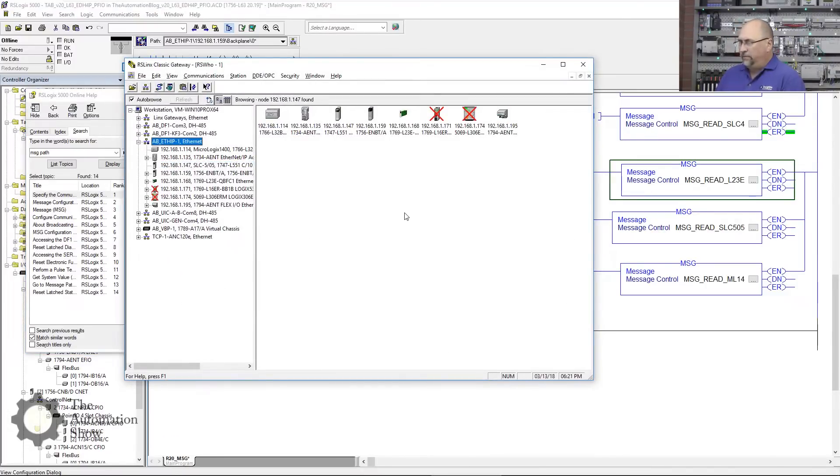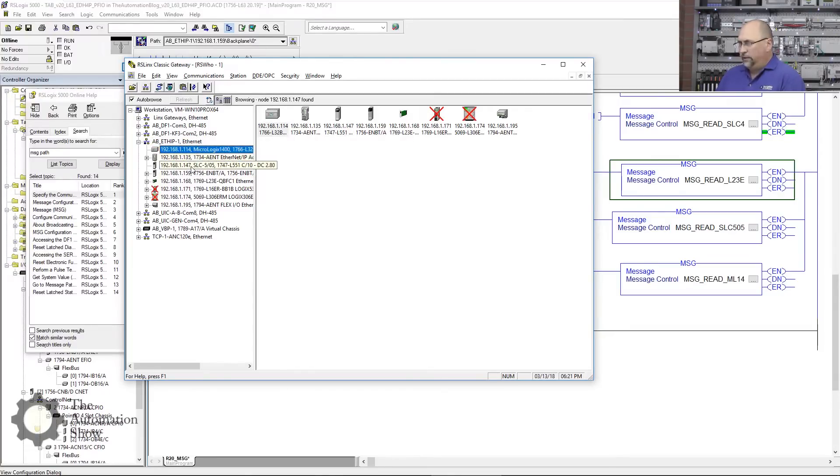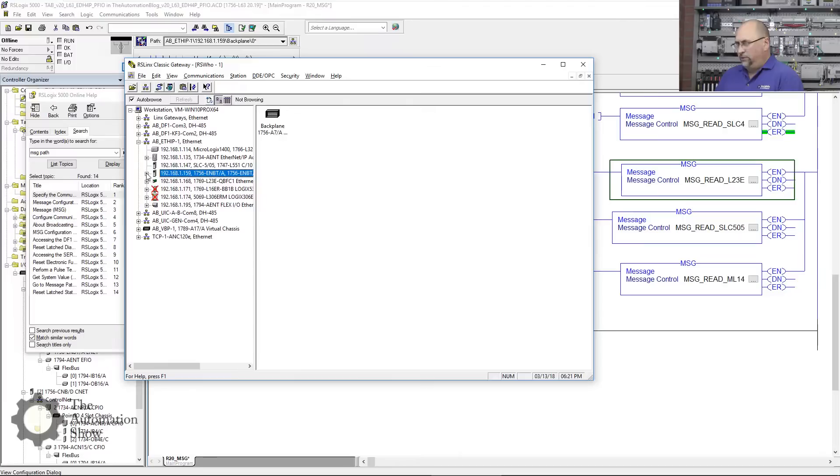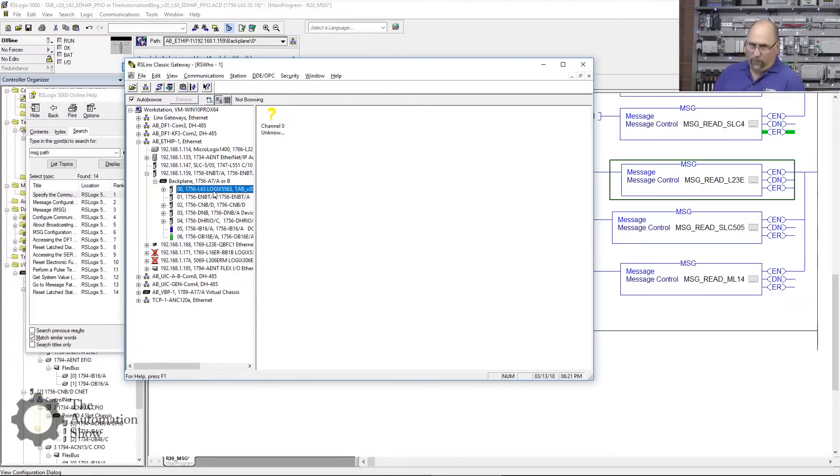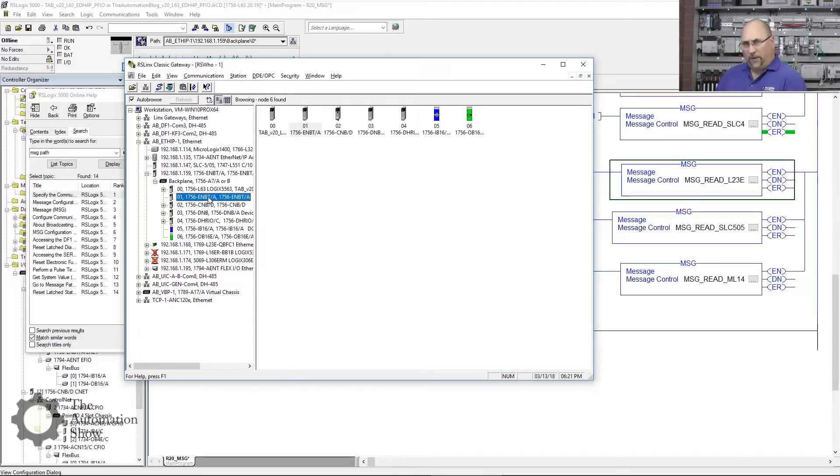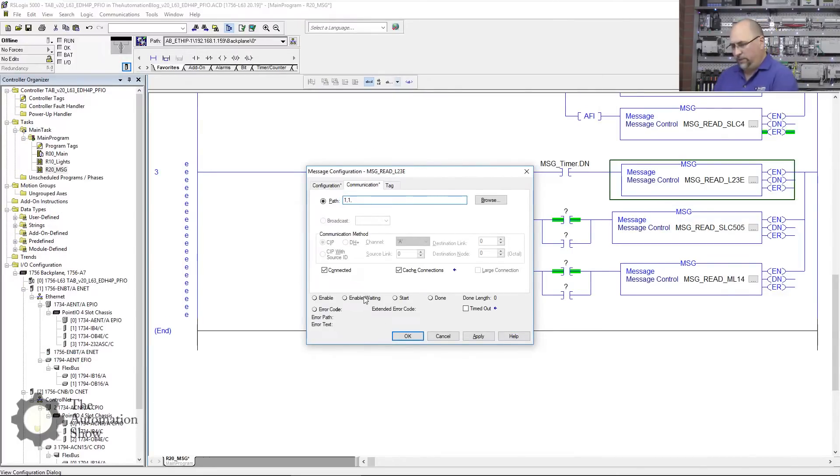Here we can see my Ethernet, my 505, my Micro Logix, and my L23 right there. The first thing I need to do is go out the backplane of the L63 we're programming and go out slot one, which is my Ethernet module. So those are the first two pieces I need. Backplane will be one, and then it's the slot number, which is also one. So we'll come back here and put backplane Ethernet module.